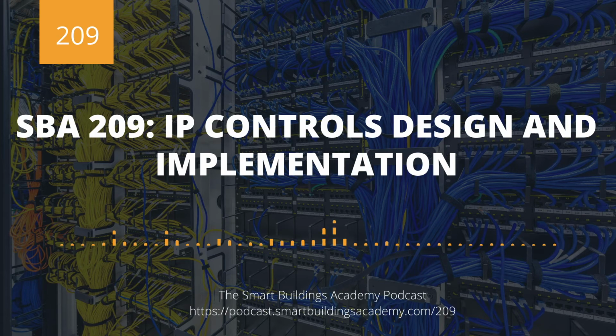The only downside of this, and folks are rectifying this, but if you recall, with MSTP controllers or LAN controllers, if you lose power to the controller, the communication buses are often electrically bridged, so they will still communicate to one another, right? They will communicate down the trunk, regardless of if the controller's on or off.